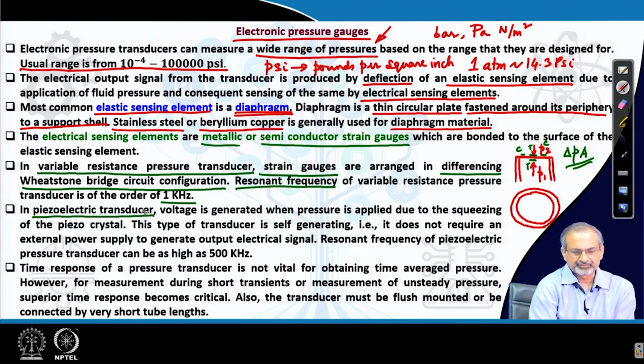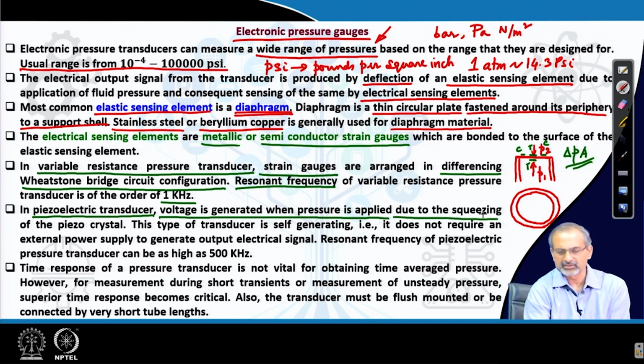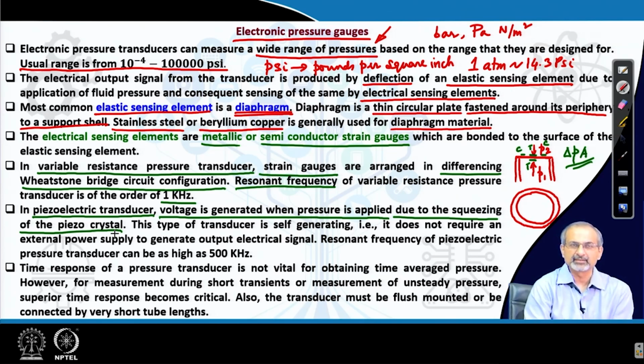There is another category called piezoelectric transducer, where voltage is generated when pressure is applied due to the squeezing of the piezo crystal. That means the applied pressure is squeezing a crystal, and that helps in generation of a voltage. Therefore, these kinds of transducers are self generating. That means you do not need an excitation voltage for them to respond and give you an output voltage. They can generate their own voltage based on the applied pressure. Therefore, the output electrical signal comes on its own. They are very high in terms of resonant frequency, which can go up to 500 kilohertz or even more, in the megahertz level.